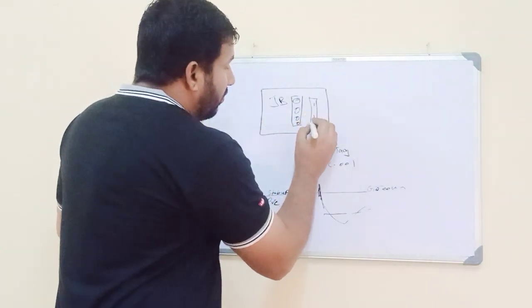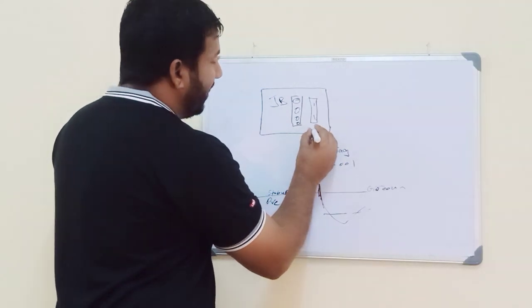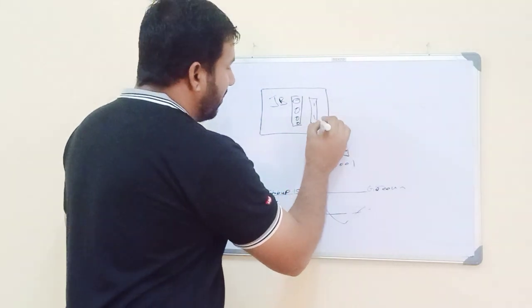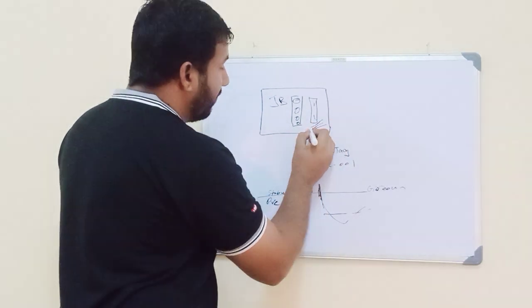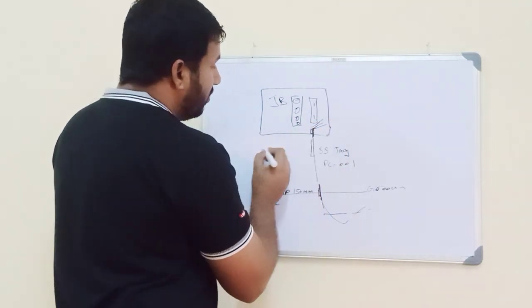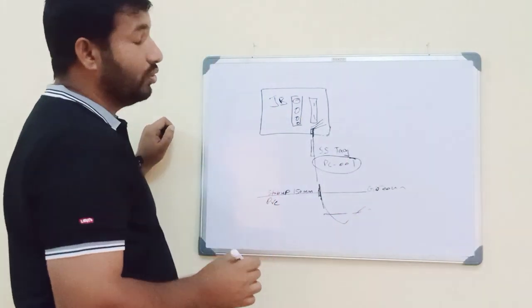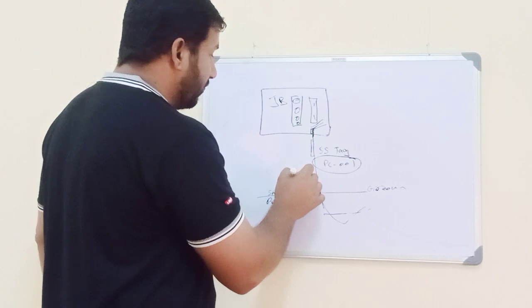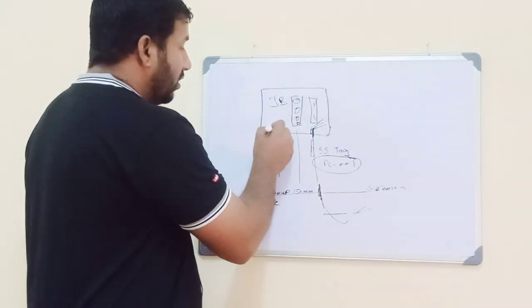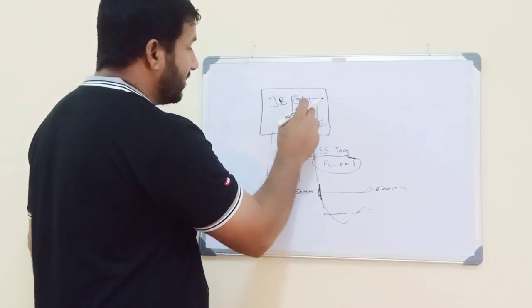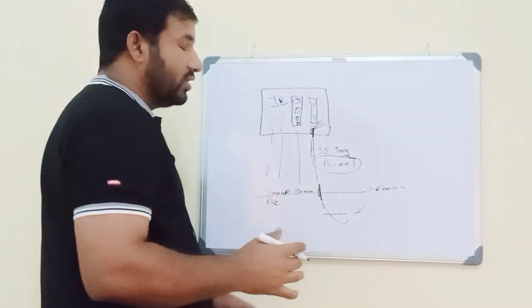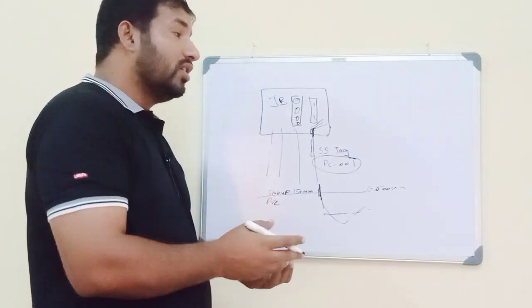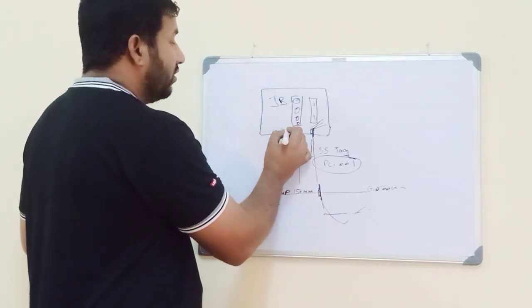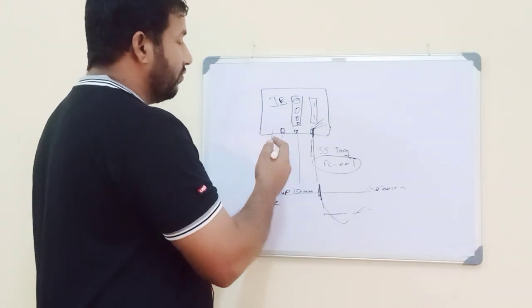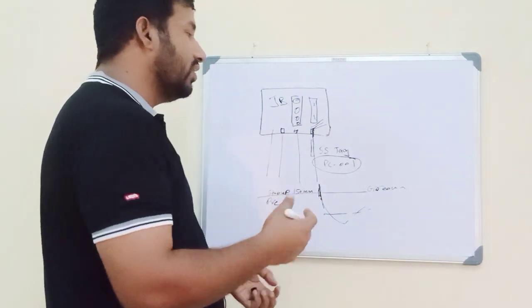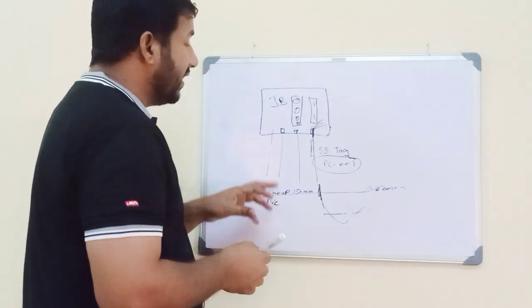After that, once the cable enters through the gland here, then it becomes like 3 core or whatever, however many - then we have to use a PVC tag here too. The same tag number should be there, because if 3, 4, or 5 cables enter, how can we identify them inside the JB? Even a control panel or any other panel should have a PVC tag here - a PVC sleeve tag, tied with a PVC tie onto that cable.